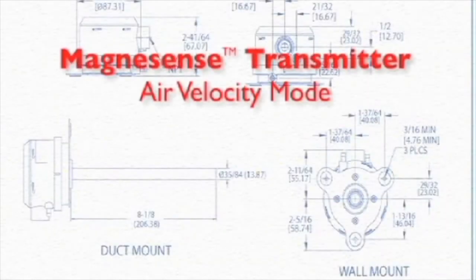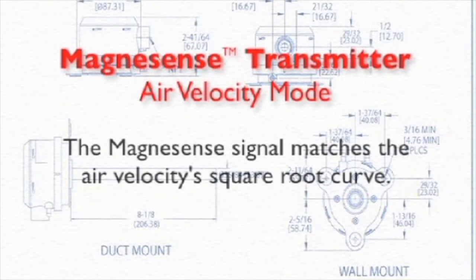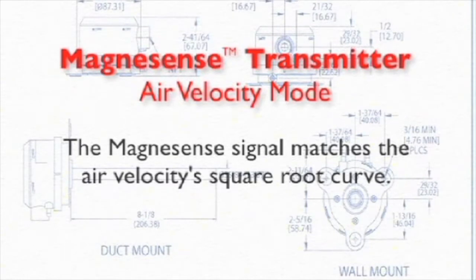One great feature of the Magnesense transmitter is its ability to be switched via a jumper into an air velocity mode unit. In this mode, the Magnesense transmitter will produce a signal that will actually match the air velocity's square root curve itself, thus not requiring any additional programming at another device.